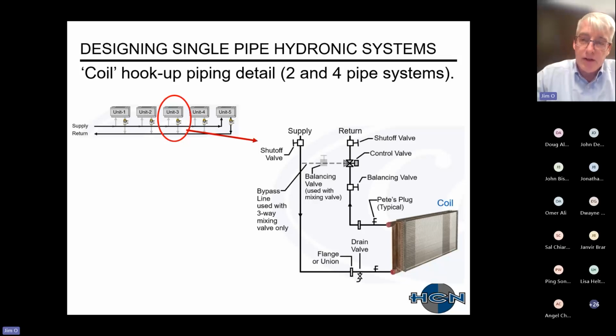And then there's also a control valve. As the name describes, the control valve is controlling the water flow, controlling the capacity, controlling the temperature of the coil. Just to point out that maybe there should be a strainer on the inlet to the control valve here, and then also maybe there probably should be an air vent to expel some of the air that's in the system.